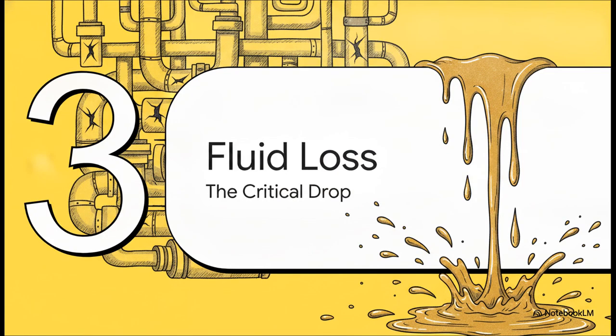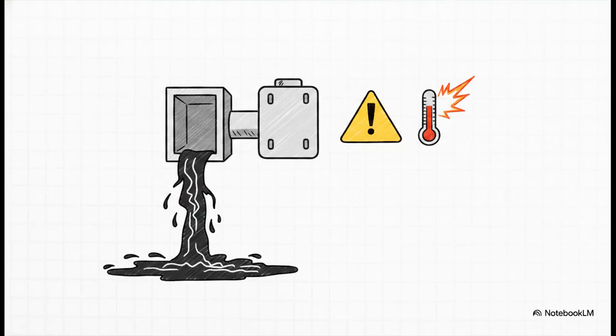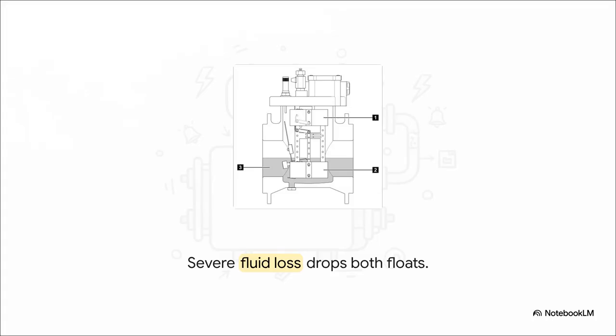Section 3. Reacting to fluid loss, the critical drop. Now, a massive drop in insulating fluid is incredibly dangerous. Without it, the whole transformer can rapidly overheat and fail catastrophically. The relay is uniquely designed to detect this kind of total, worst-case evacuation of fluid from the pipeway. If the fluid line completely plummets, the oil has drained out so much that both the upper and lower float mechanisms are just left hanging there, totally exposed in an empty chamber.